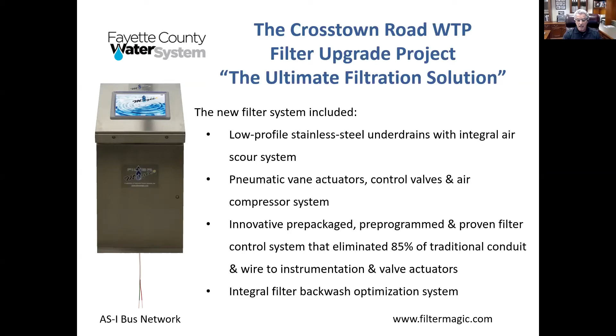Also, as a part of FilterMagic, one of our patented aspects is that we utilize an AS-I bus network, which means actuator sensor interface. Perfect. That's what we're working with in the filter system, instrumentation, valve actuators. And by using that bus network from our consoles down to all the devices, we eliminated up to 85% of the traditional conduit and wire. Now, they didn't have any conduit and wire, as you saw in the previous pictures. They were going to have to put these conduit and wires in there. And that was going to cost a lot of money. And we estimate that across 8 filters, it saved them $300,000 to $400,000 in capital costs up front to eliminate all this conduit and wire through the use of our AS-I bus network, but also through the use of the pneumatic vane actuators. And again, they were able to get an integral filter backwash optimization system that was proven built into their system.